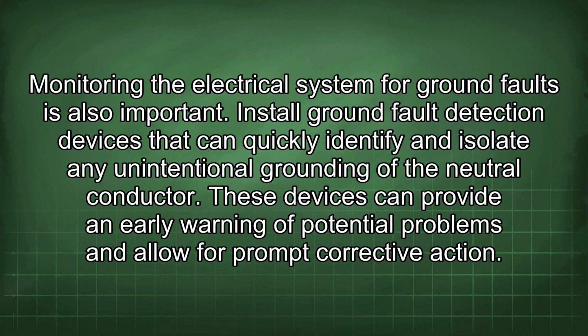Monitoring the electrical system for ground faults is also important. Install ground fault detection devices that can quickly identify and isolate any unintentional grounding of the neutral conductor. These devices can provide an early warning of potential problems and allow for prompt corrective action.